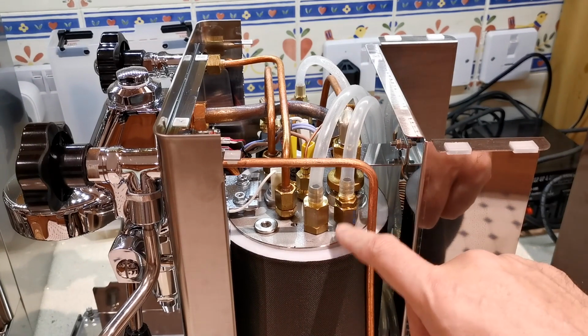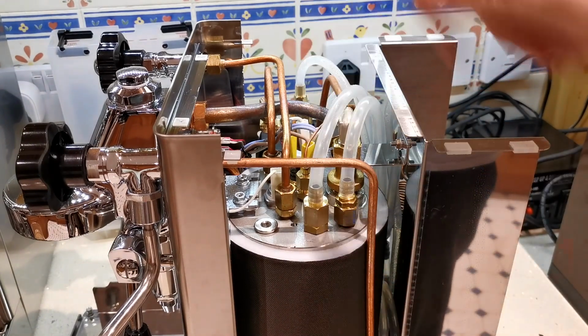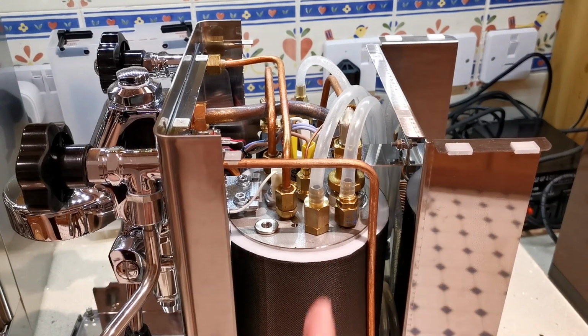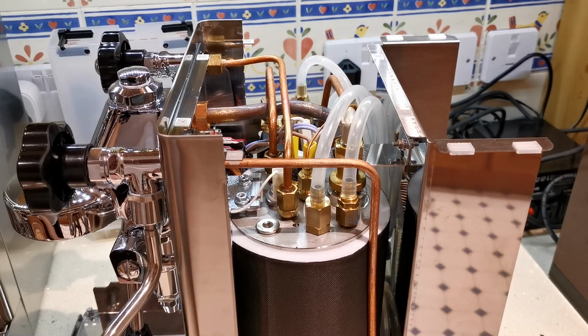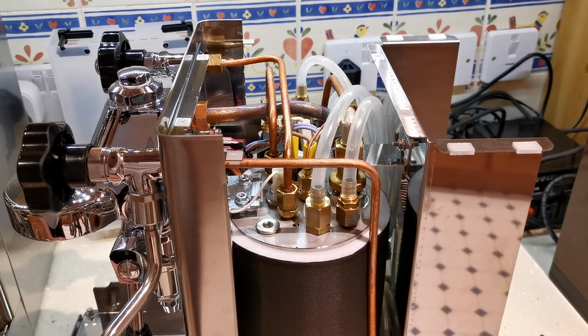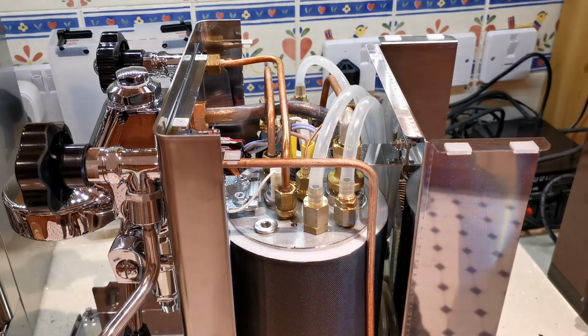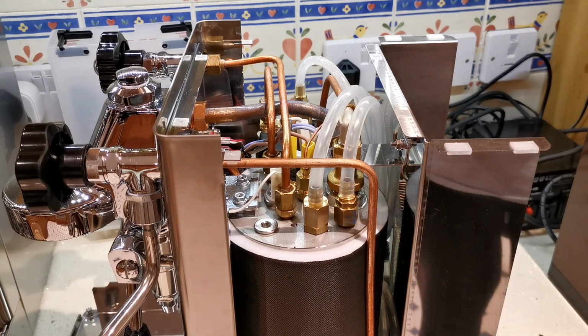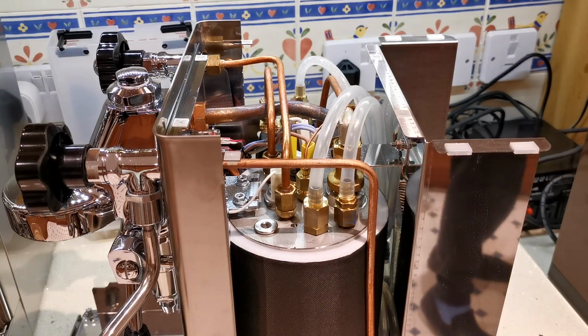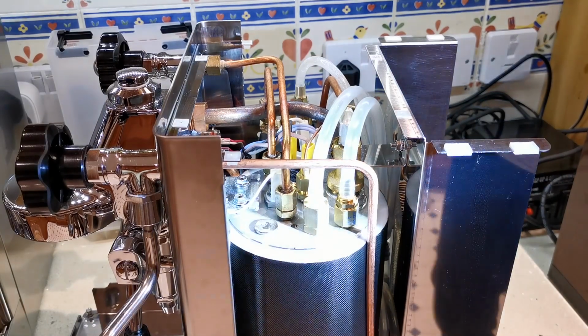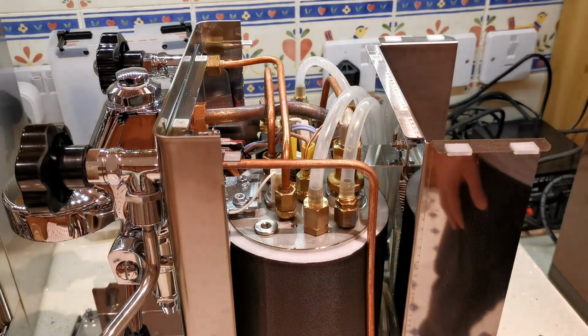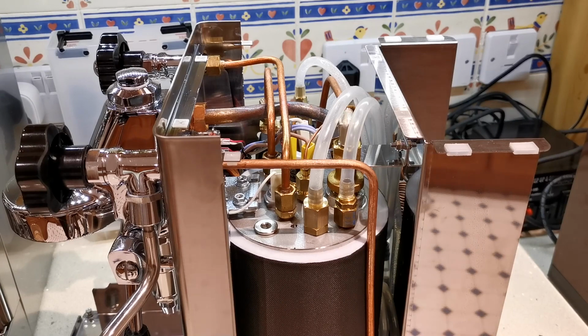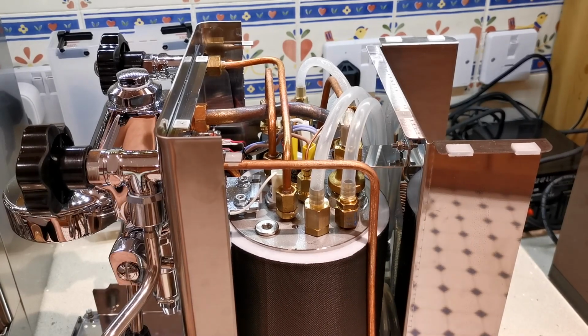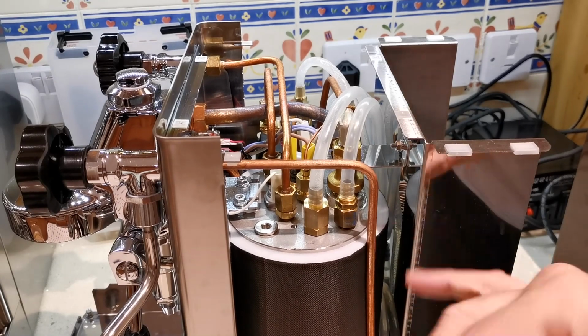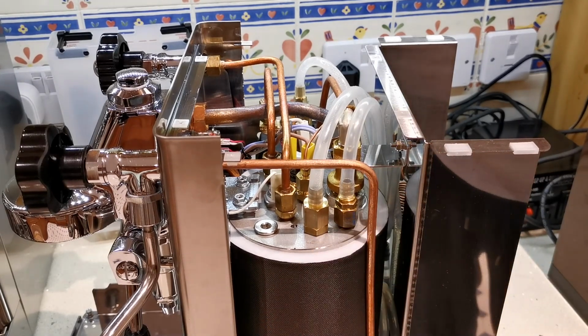So here we are at the main boiler. So you've got your various components here. One, you've got your pressure relief valve, and you've got your vacuum breaker. Now I just need to have a good close look at the pressure relief valve. I think they use quite a high rating. Yeah, pressure relief valve rating is 3 bar, which is good because sometimes this system can get pretty hot. It can get up to quite a good temperature, you know, quite a good pressure. So 3 bar is extremely reassuring because when it does its first warm up, it really does get hot. I think it got up to about 2.5 bar, and sometimes a lot of these pressure relief valves are actually 2.5 bar. So it's nice to see it's 3 bar.